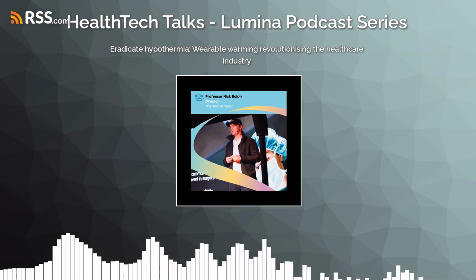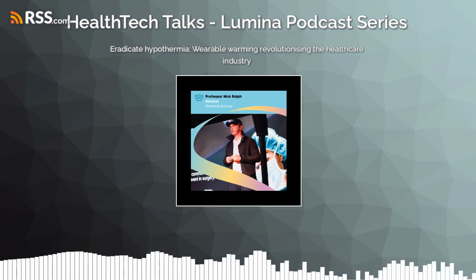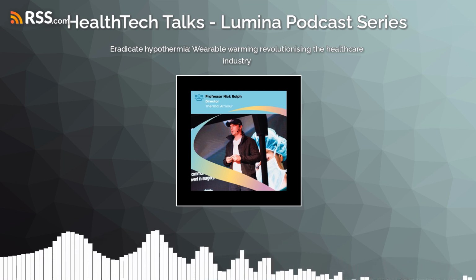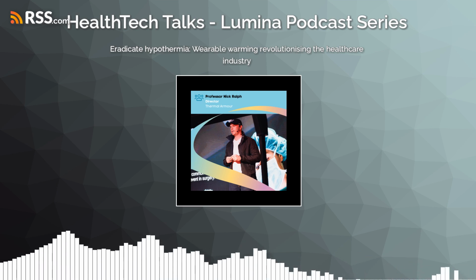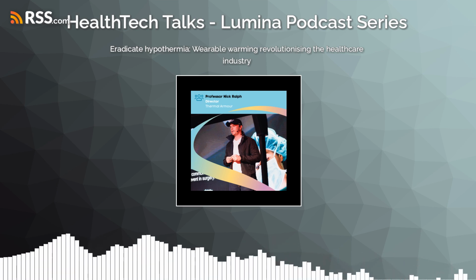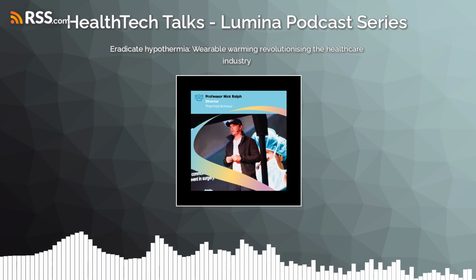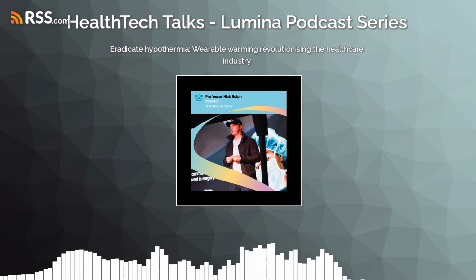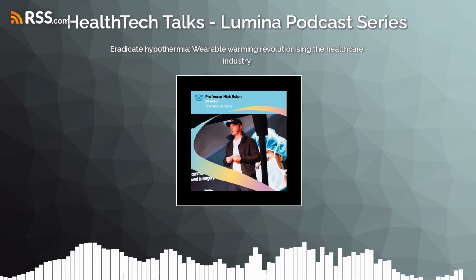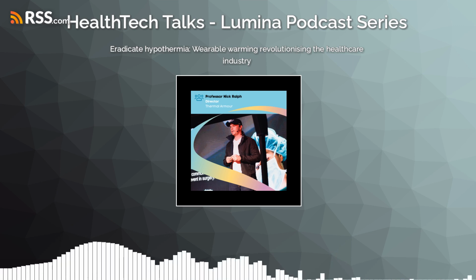There's many studies that have proven it's safe and effective, but there are also some concerns that are emerging in the industry. So we know from studies that patients lose about 140 watts of heat, and the current devices are really only getting about half that much back into the patient. So what's now happening is we're slowing down surgery because we're having to warm patients for at least 30 minutes beforehand. And what we found in a recent study that we've just done is some of those devices take up to 50 minutes to heat up. So any of the pre-warming that's happening is just not effective at all.